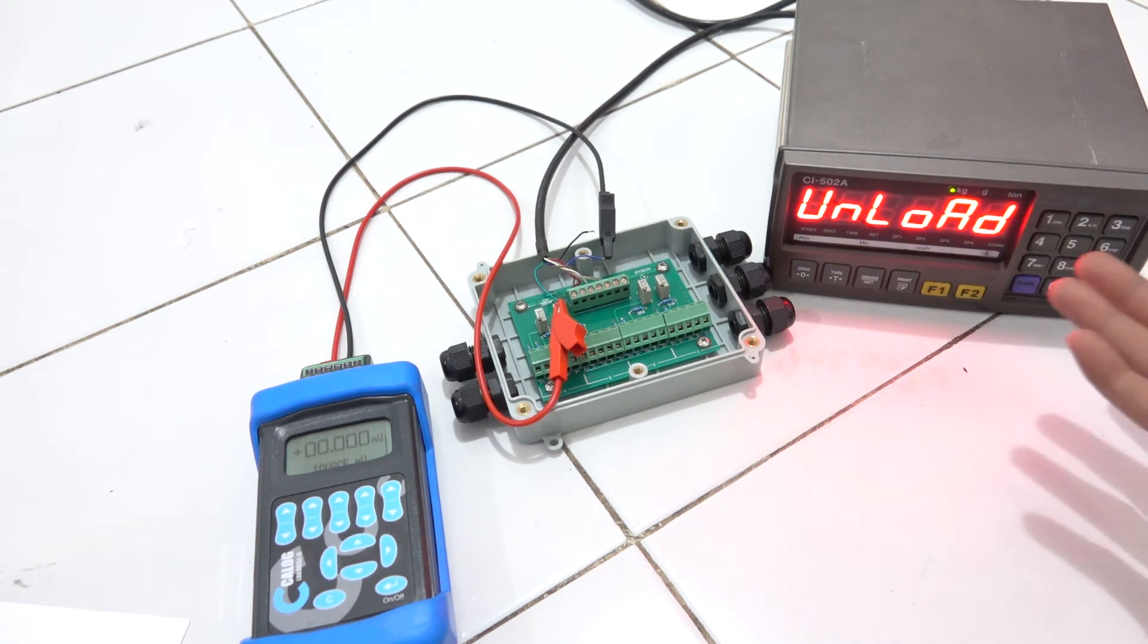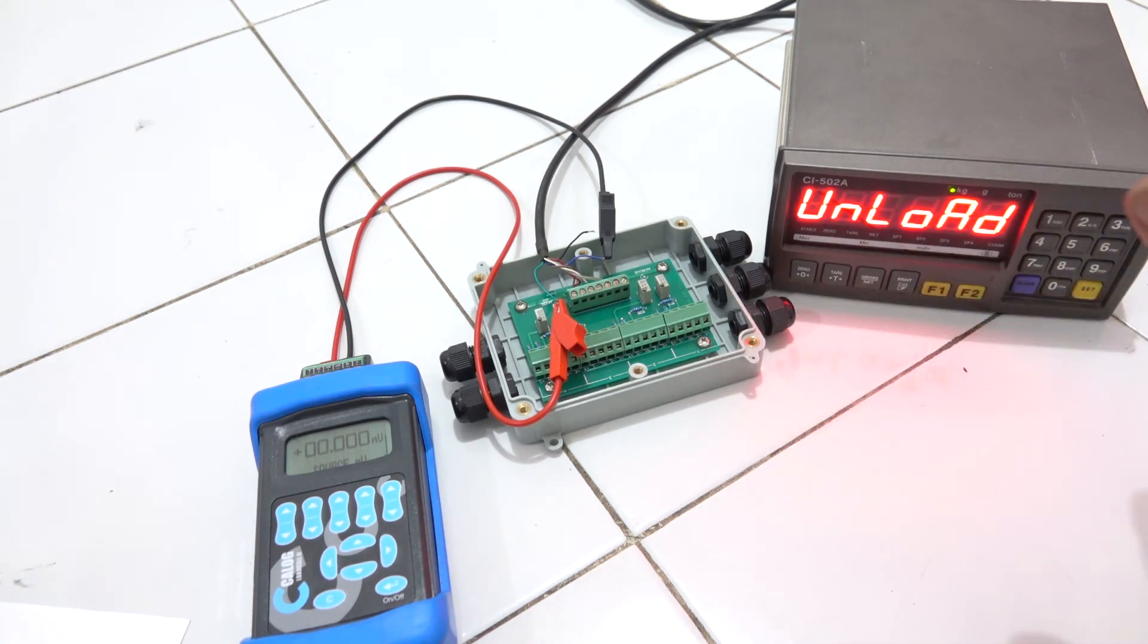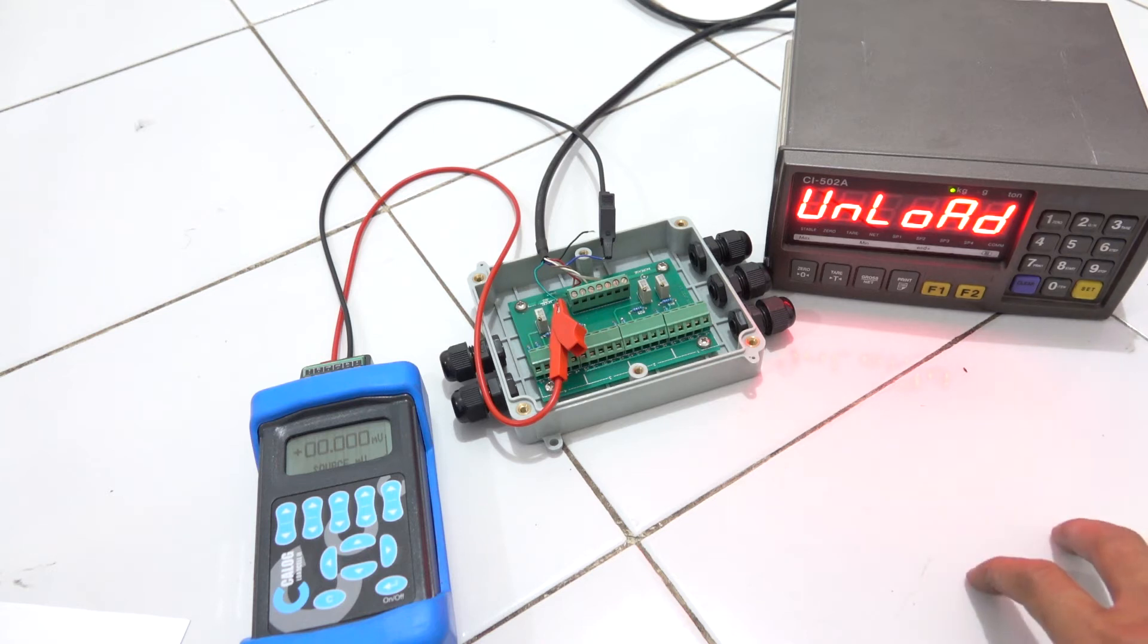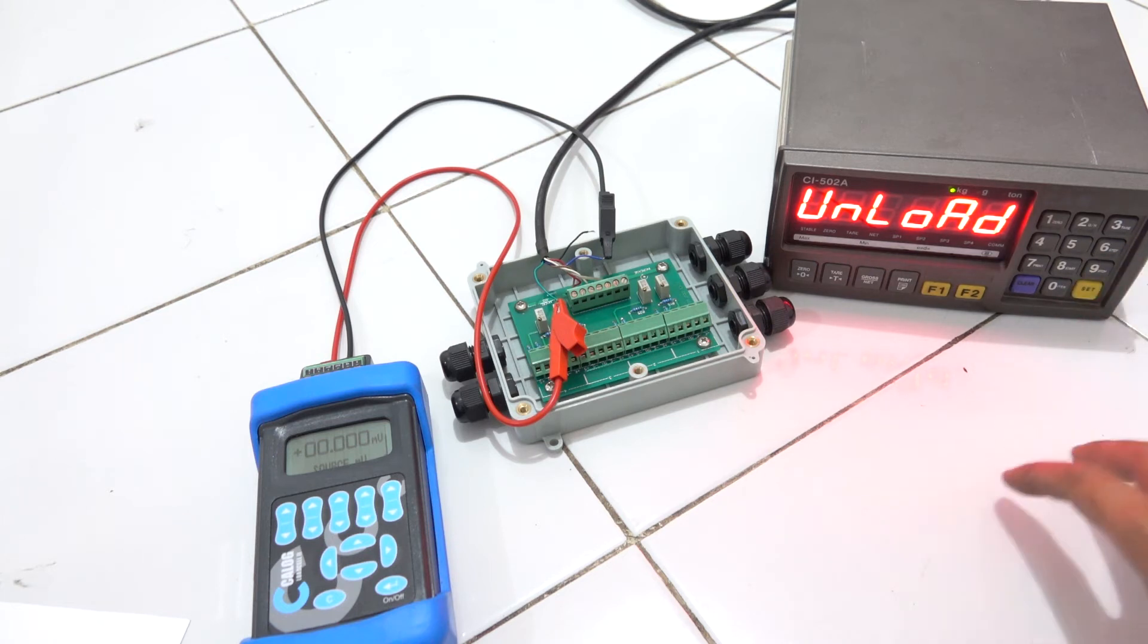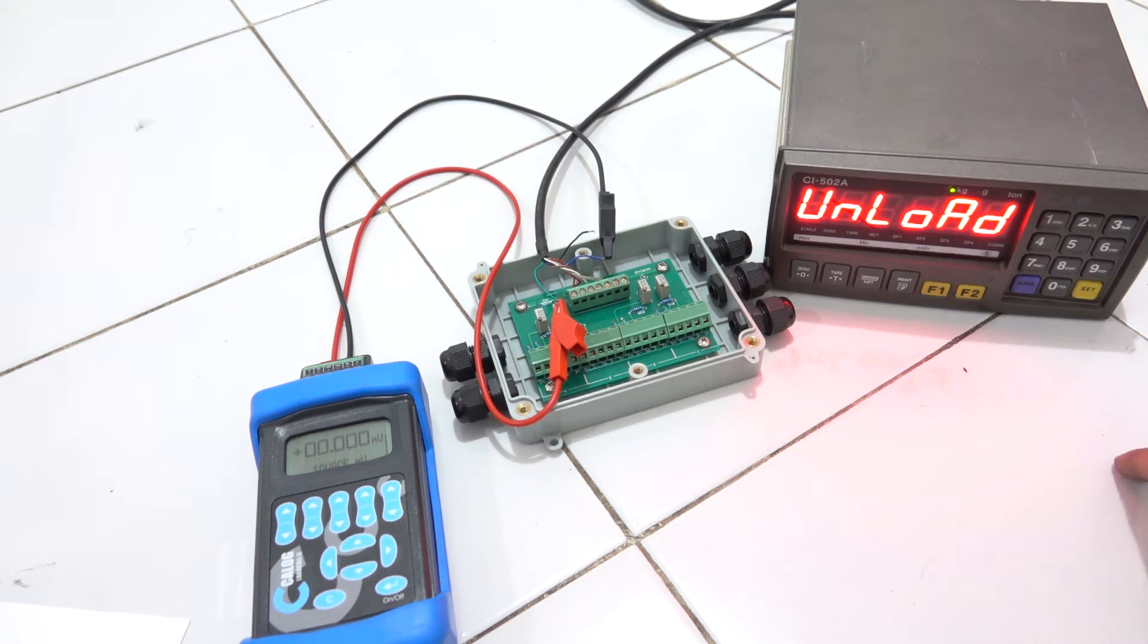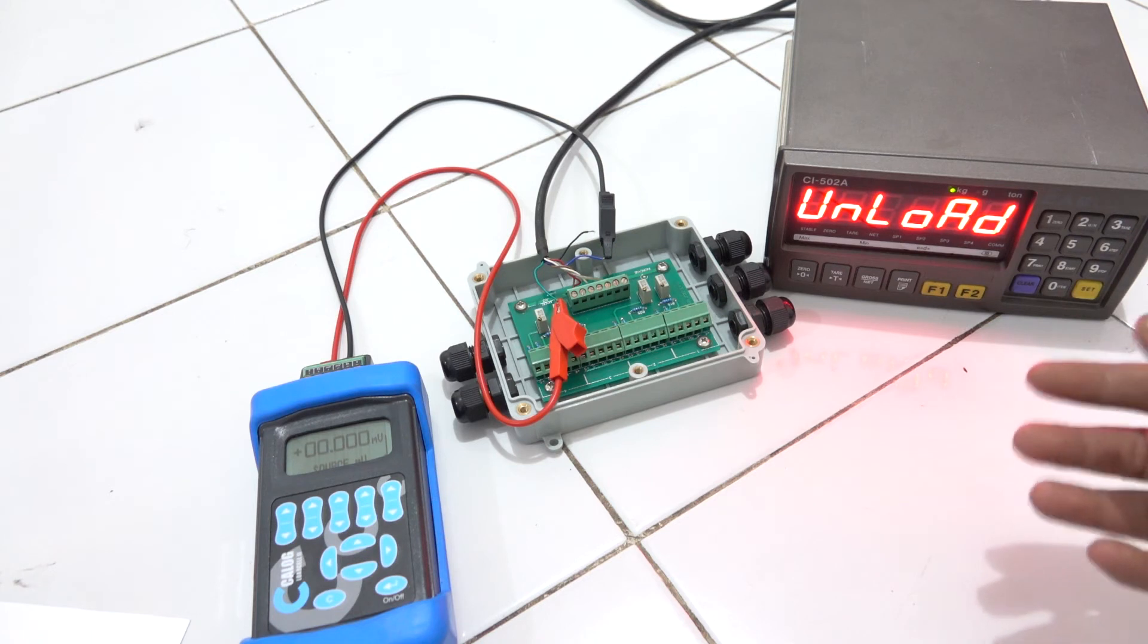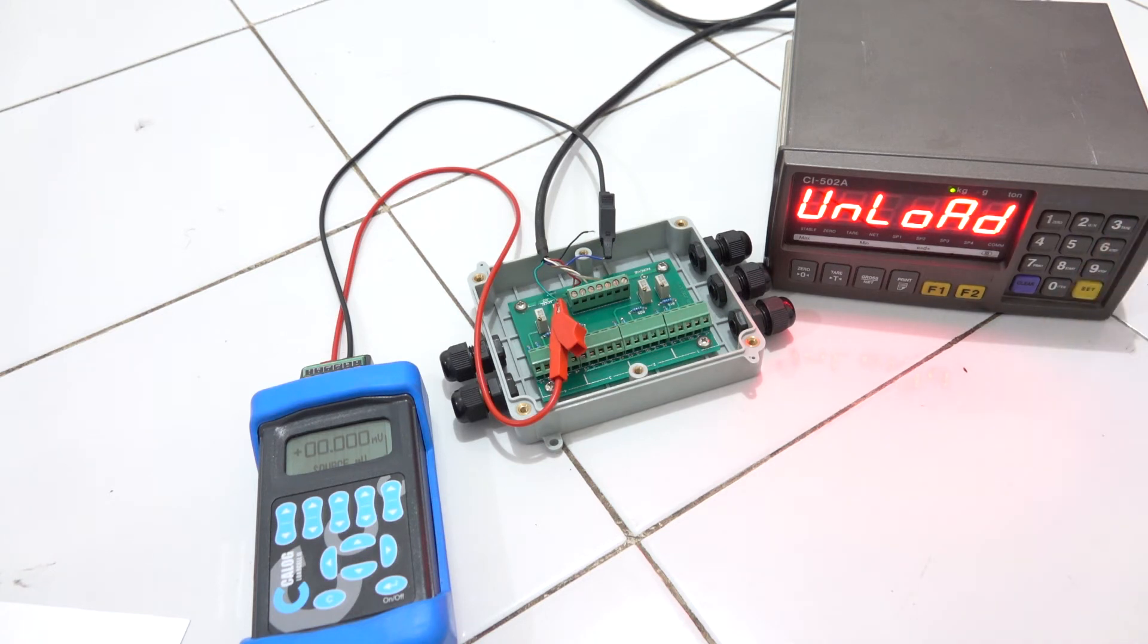And they say unload means no load at all. So no load at all means that the load cell must generate zero millivolt. Of course, zero millivolt - of course there is a division, maybe 0.001. But based on national standard, there is a maximum plus-minus 0.1 percent. You cannot do a calibration with zero load but the voltage generated is one millivolt.